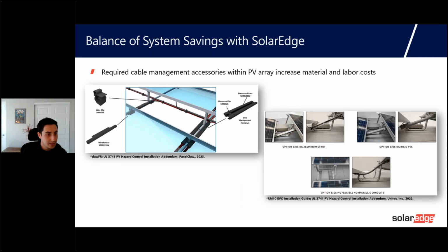Another consistent reason for balance of system cost increase is the specialized racking. The SolarEdge DC optimized solution is basically agnostic to the racking that's used, and doesn't require any special racking to be 3741 compliant. However, the listed racking solutions that are not DC optimized use a number of accessories that limit exposure to high voltage cables, often between rows or between columns of the PV array. As well, they have special accessories to maintain gaps between those cables and any metal on the PV frame or the racking structure. There are a couple of images up on the screen here that show examples that exist in the market of how those mechanical protections need to be put in place for 3741 compliance.